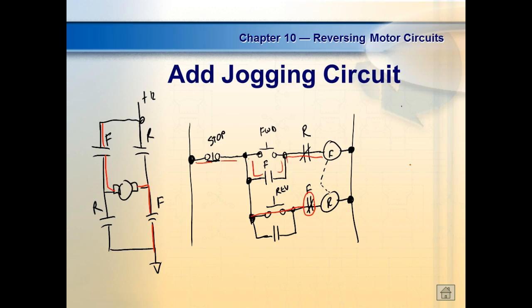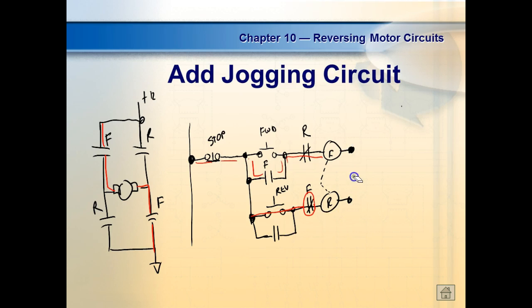Just now we would buy 3-phase contactors, right? You understand that? We'd make sure our 3-phase contactors have at least one auxiliary contact on them, because we need an auxiliary contact for the sealing. And ours has this. Now, normally, if I go to a dual voltage three-phase motor, it means we've got to have external overloads, because we can't have internal overloads on a dual voltage motor. Y'all understand why? Why is that?